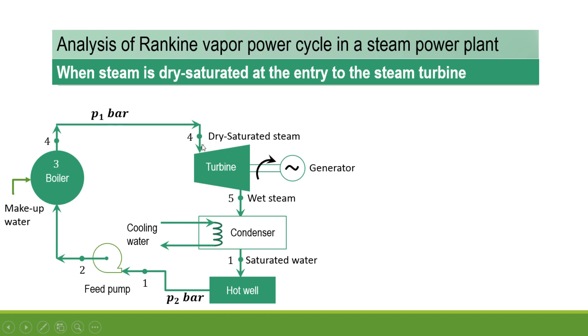After isentropic expansion in the steam turbine, the dry saturated steam gets converted into wet steam, which is then provided to the condenser. In the condenser, cooling water is supplied and absorbs the latent heat from the wet steam, converting it to saturated water. This saturated water is stored in the hot well, and from the hot well it is fed back via the feed pump to the boiler. Make-up water is provided to maintain the predetermined water level in the boiler.